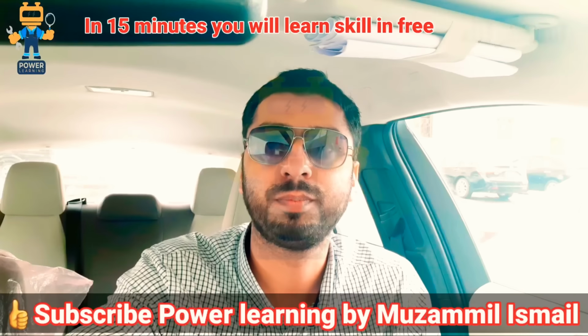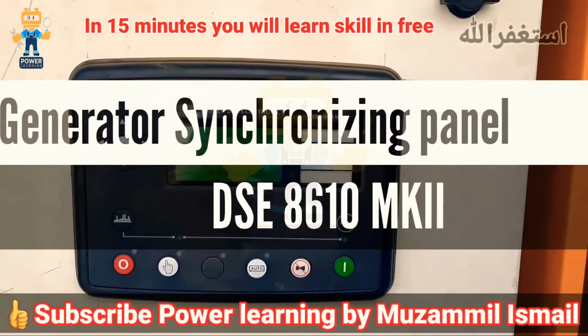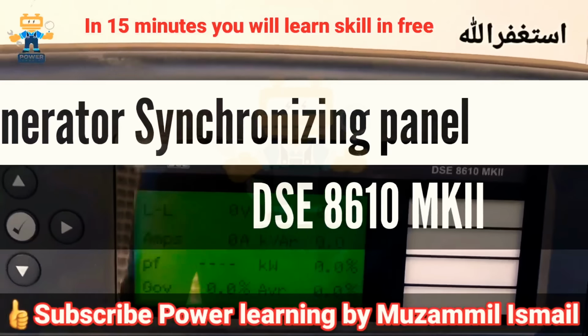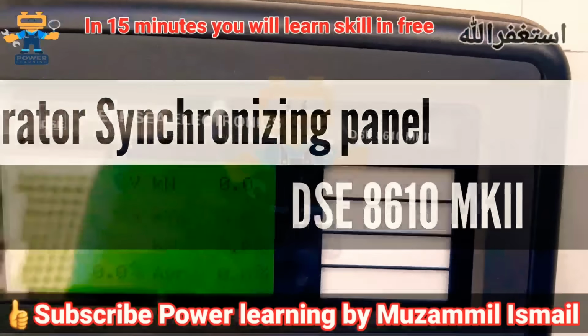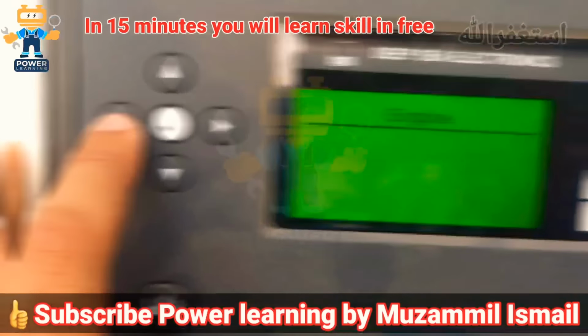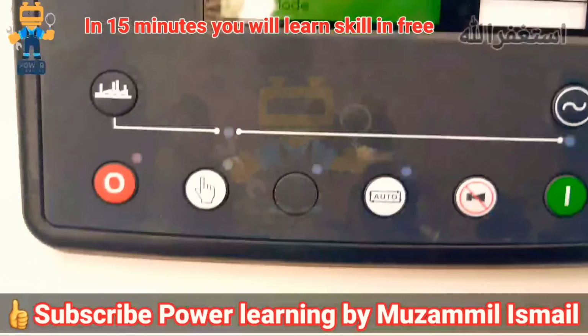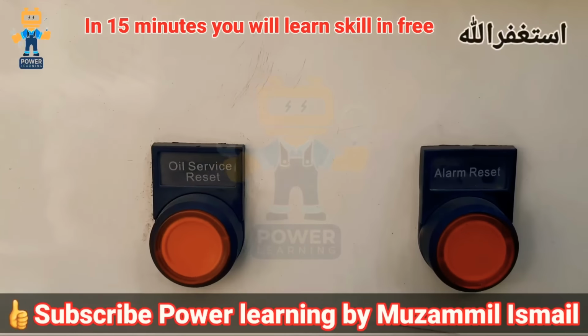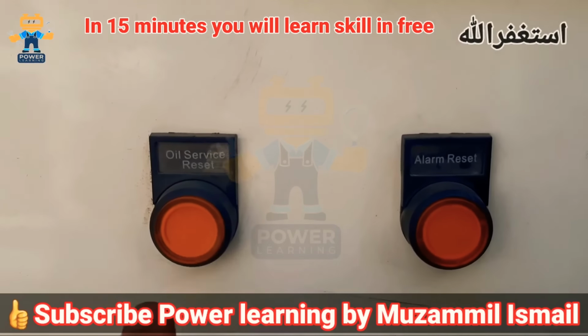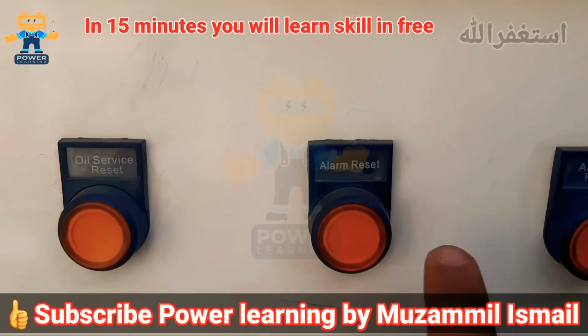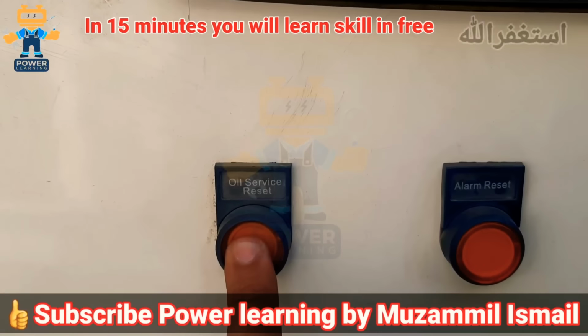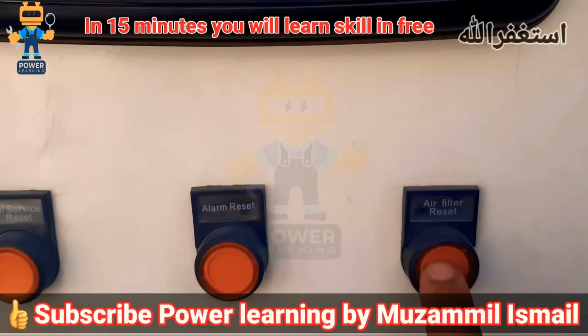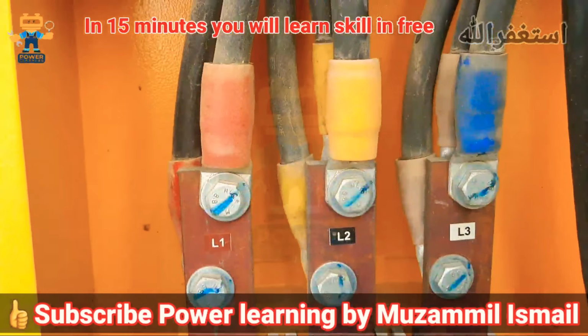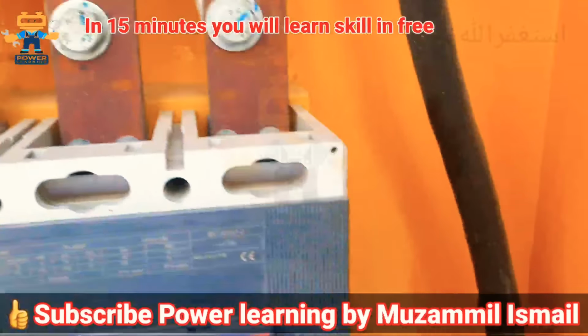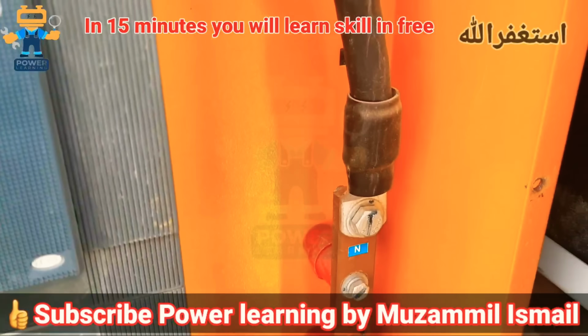Start the video. Hello, assalamu alaikum. So this is our DeepSea 8610 and here is our generator at rest. Here we have 3 indication push buttons: oil service reset, alarm reset, air filter reset. After that here we have our main breaker, line 1, line 2, line 3 and the neutral here.